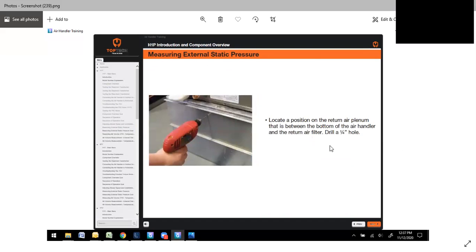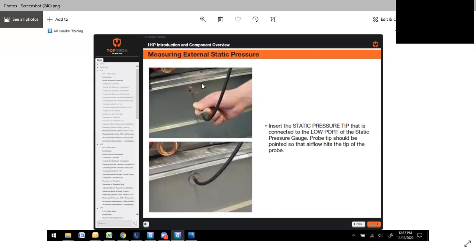Now we're going to go to a position on the return side. There again, drill a 1/4-inch hole. Then we're going to install a second pitot tube, and we're going to install that on the low port or the negative side of a digital manometer. The probe should be pointed so that the airflow hits the probe directly.